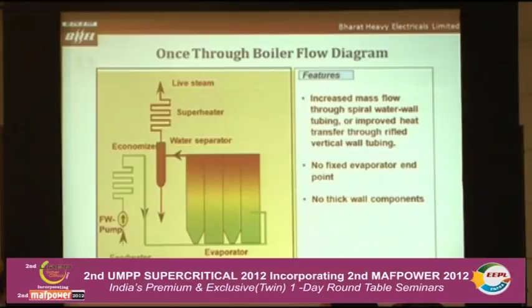The feed water comes through the economizer, then it goes to the water wall, separator, and superheater. During normal operation, this part of the circuit is switched off. Below 40%, because of the intense heat flux felt in the water wall, we will have to use a small recirculation. With this, a small circulation pump is also there. This is the characteristic of this once through boiler, because it is used up to 30-35% of MCR. After that, this system is switched off and it is only in once through mode. And the normal operating range is anyway 50% BMCR to 100%, so it doesn't matter.